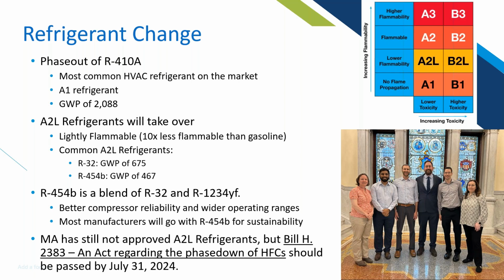Those 2 refrigerants that are going to be big players are R32 and R454B. R32 has a GWP of 675, while R454B is 467. Now, don't get it confused though, R454B is actually mostly R32. It just has some R1234yf, which is a hydrofluoroolefin. It's kind of a better refrigerant because it provides better compressor reliability in wider operating ranges, and also has a lower GWP. So most manufacturers that work with refrigerant will be going to R454B for sustainability purposes.